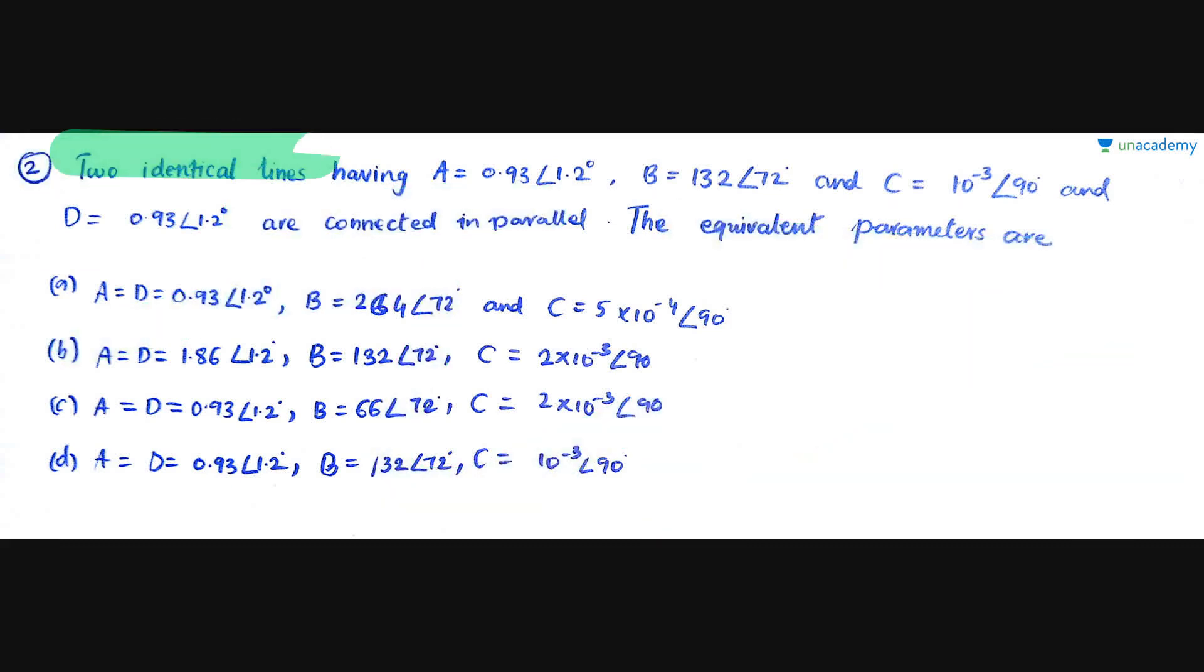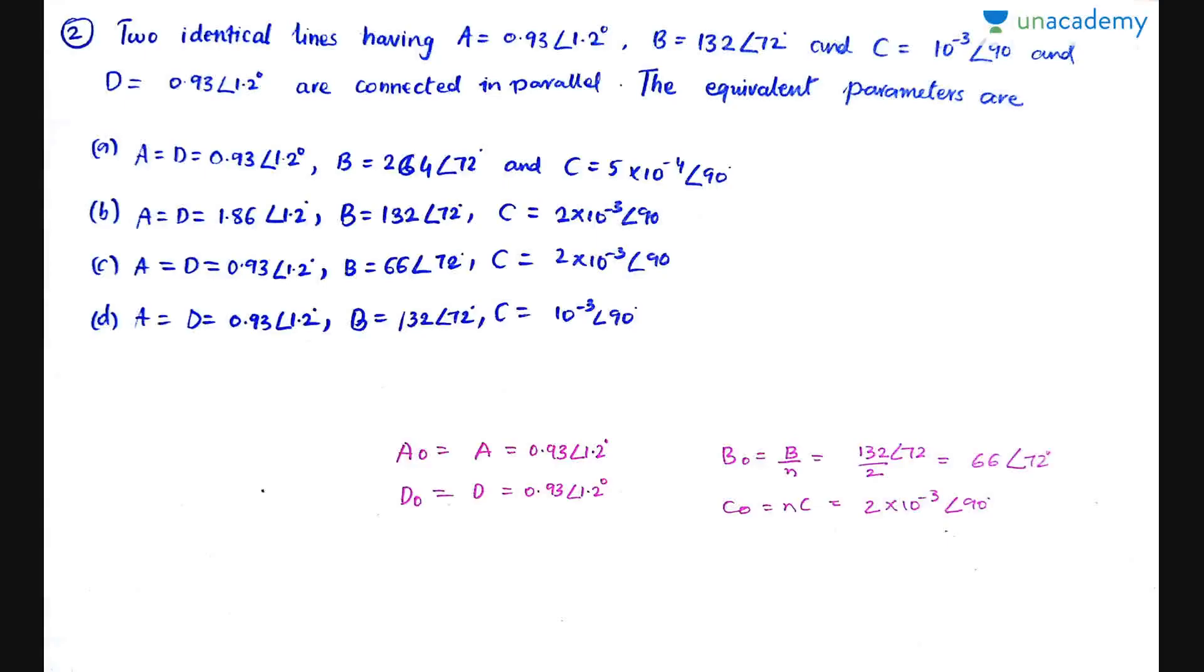It's telling that it is two identical lines. I hope you remember the overall parameters of N number of identical lines. For any number of identical lines connected in parallel, A0 or D0 will be equal to the original values. So A0 equals A, that is 0.93 at angle 1.2. D0 equals D, that is 0.93 at angle 1.2. And B0 will be B by N. What is N here? Two networks. So 132 by 2, which is 66 at angle 72.